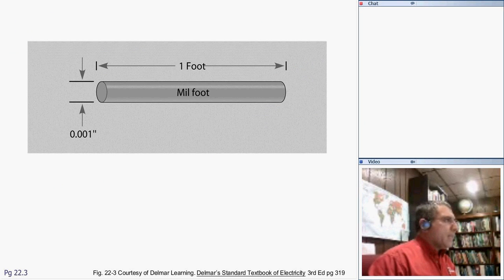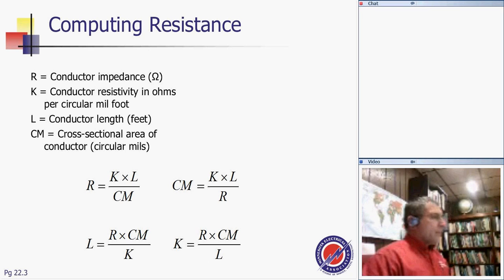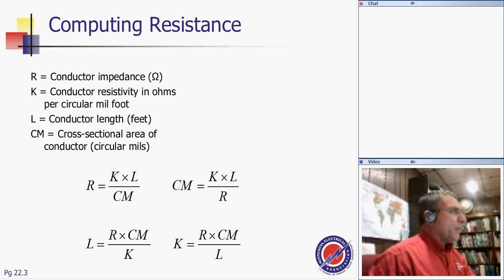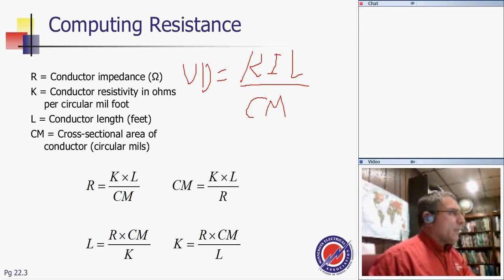The conductor, this talks about, guys, the cross-section area. When we size based on voltage drop, I want you guys to highlight a few things here. The most important thing that I highlight is there is a formula. Let's use a different color here. For voltage drop, voltage drop equals K, based on this one, K I L over CM. This is an important formula, guys, to find the voltage drop for the conductor.